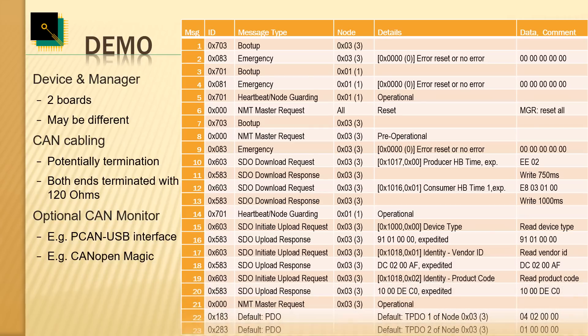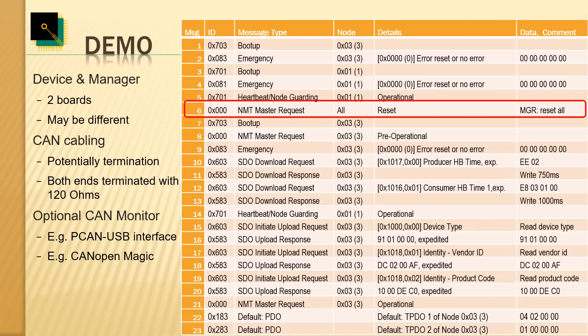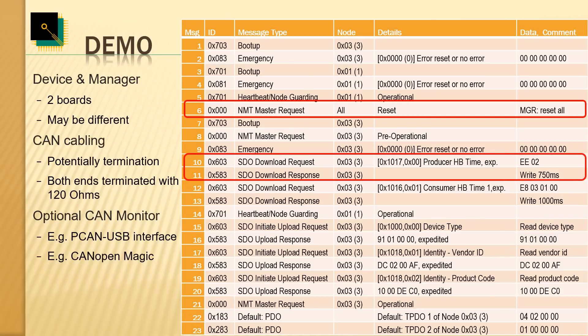This table contains a trace recording generated with CANopen Magic. From left to right the columns are: message number, CAN ID, message type, node ID involved, and a detailed interpretation of what the message does. For example, line 6 shows CAN message ID zero — the highest priority message in the CANopen system — which is the Network Management master request. Here it is a request to all nodes to reset, ensuring a clean fresh start after powering up. Lines 10 and 11 show an SDO — Service Data Object — request from the manager to node 3 to write the heartbeat time value of 750 milliseconds.